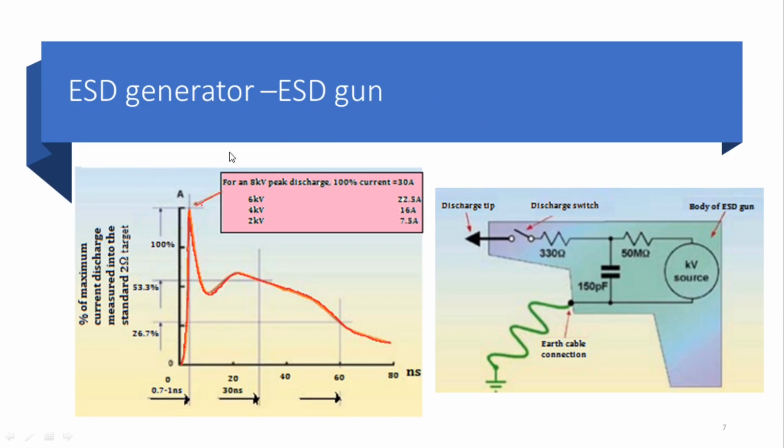So this is the waveform of an electrostatic discharge, which is generated due to the static buildup in our bodies. You can see here to the left. So the figure on the left shows the standard waveform, which is going to be used for these types of tests. And the standard uses EN 61000-4-2. That's the ESD test, which is a single unidirectional impulse.